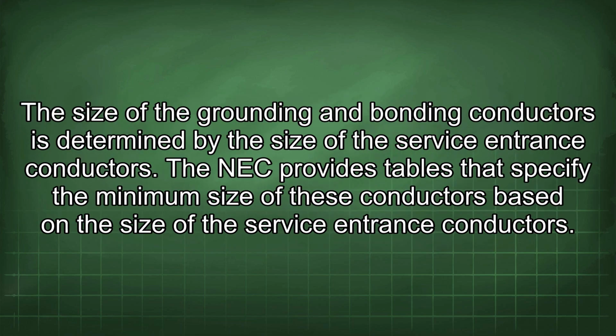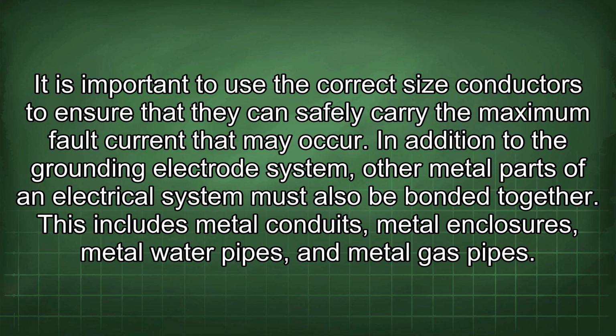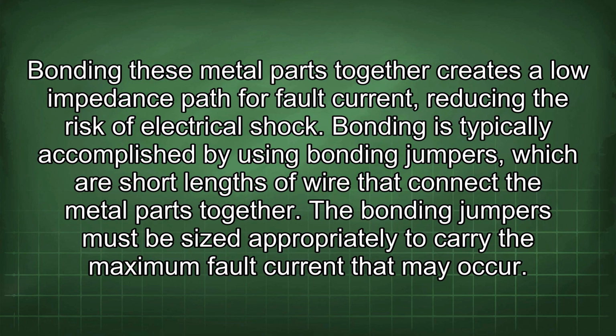The size of the grounding and bonding conductors is determined by the size of the service entrance conductors. The NEC provides tables that specify the minimum size of these conductors based on the size of the service entrance conductors. It is important to use the correct size conductors to ensure that they can safely carry the maximum fault current that may occur. In addition to the grounding electrode system, other metal parts of an electrical system must also be bonded together. This includes metal conduits, metal enclosures, metal water pipes, and metal gas pipes. Bonding these metal parts together creates a low impedance path for fault current, reducing the risk of electrical shock.